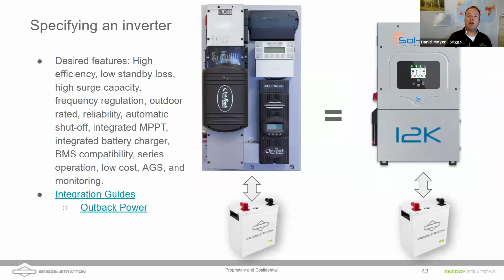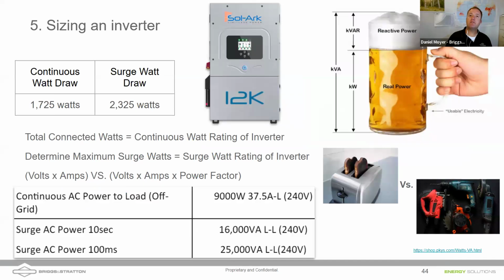Now we need an inverter. What do you want in a nice inverter? Something that's efficient, doesn't use a lot in standby, can handle the surge, ideally outdoor rated (though it doesn't have to be), low cost, and has the ability to start a generator. There are two examples here. You could absolutely still do something on the left, but with the advent of hybrid inverters, many are now on the market that let you put all the parts and pieces into one piece of equipment.